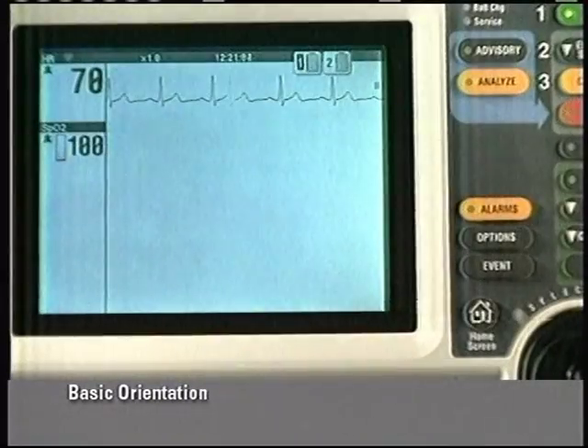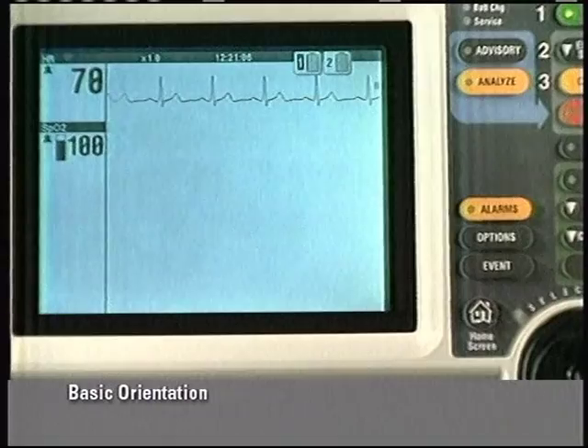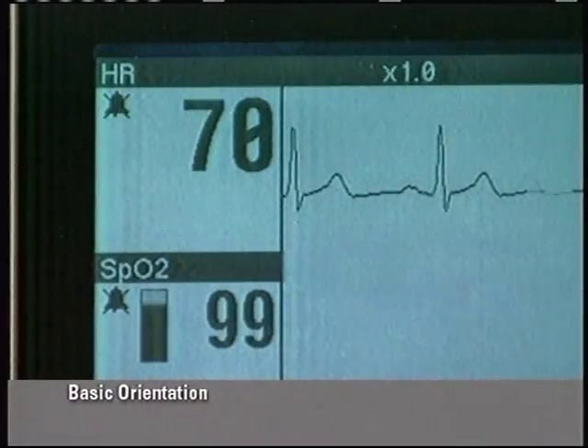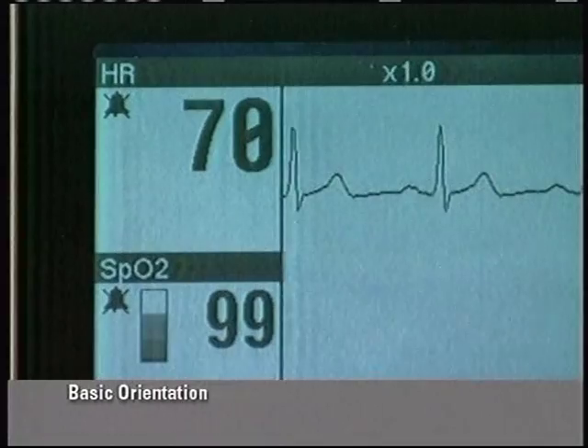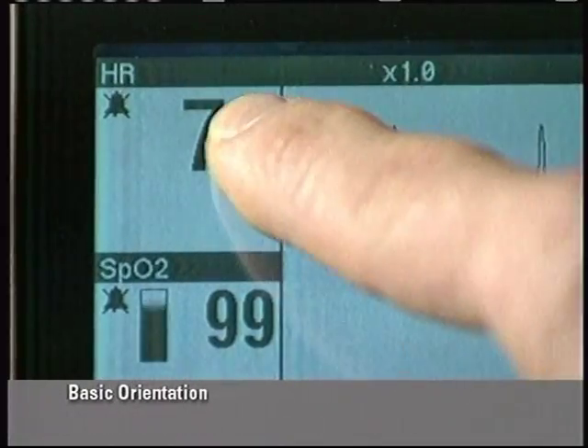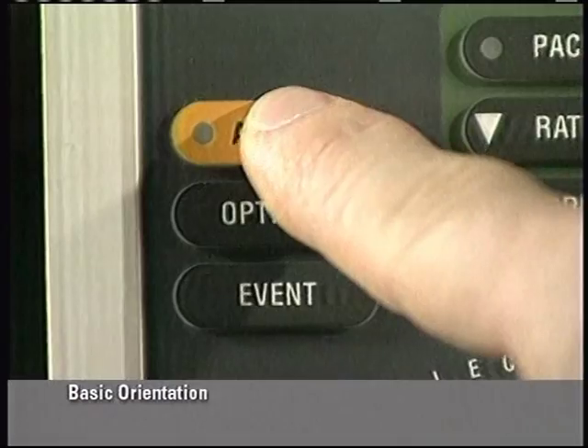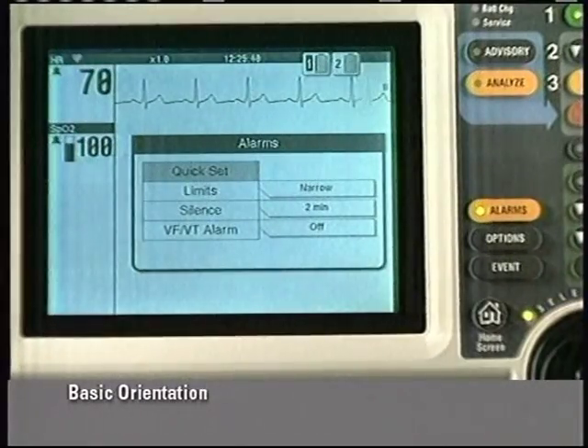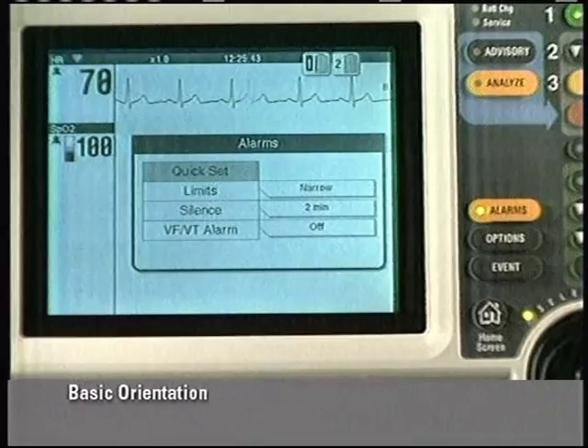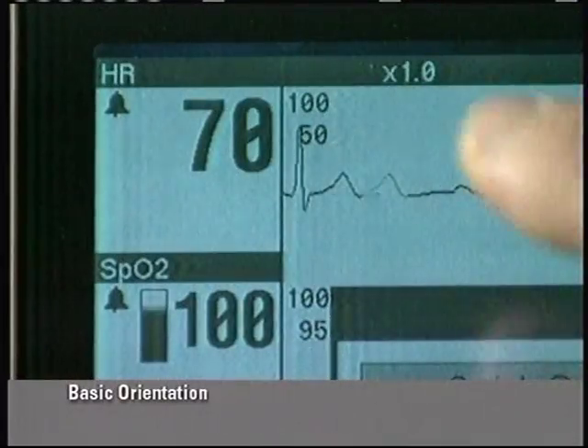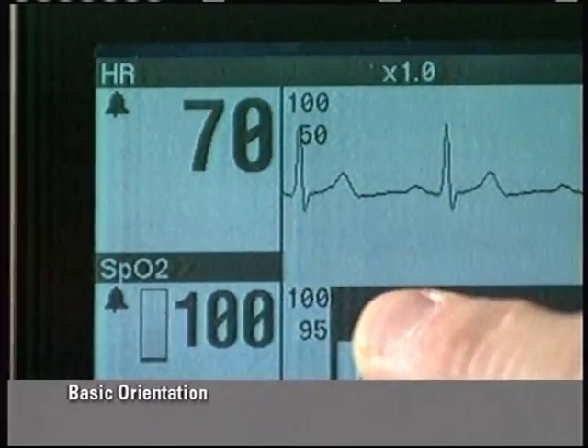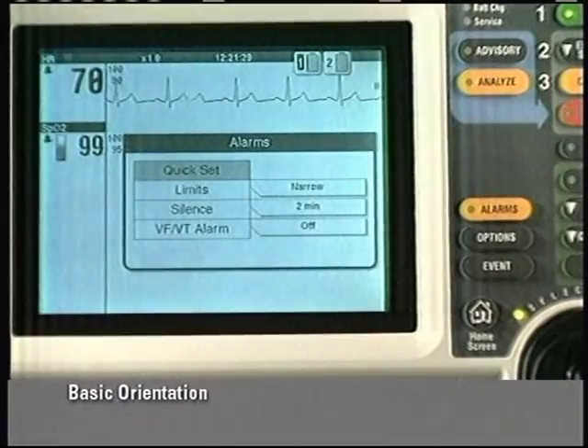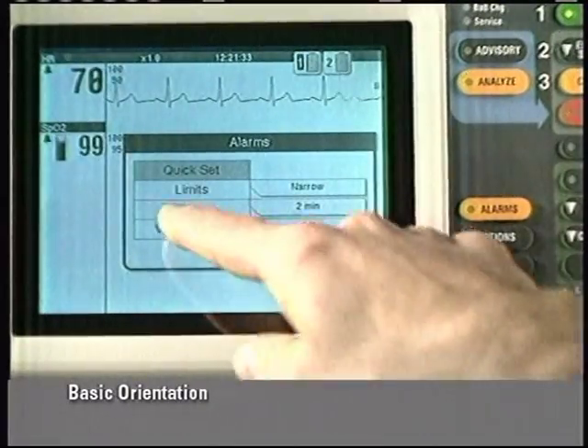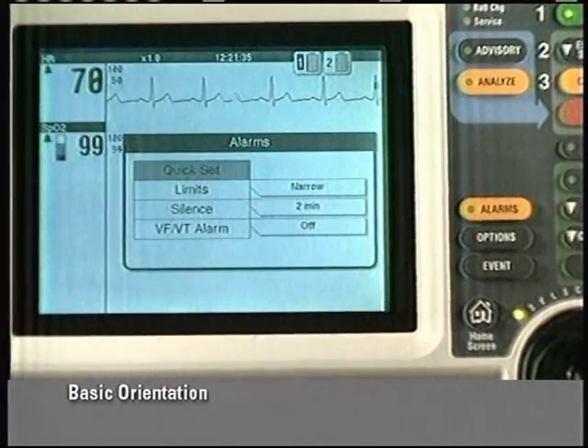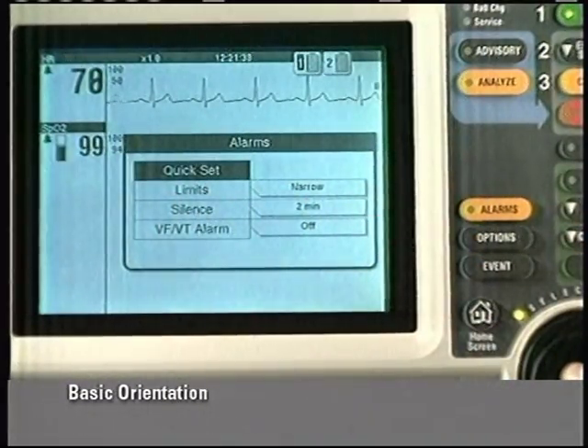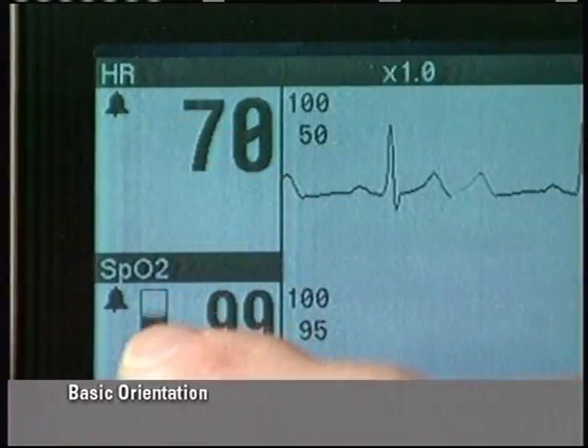The LifePak 12 defibrillator monitor features QUIK-SET alarms. QUIK-SET alarms can be configured to be on or off when the defibrillator is powered on. If QUIK-SET alarms are configured off, push Alarms to activate the alarm. The alarms menu appears. When activated, QUIK-SET automatically sets alarm limits around the patient's current vital sign values for all monitored parameters. If the limit setting is acceptable, press the selector. QUIK-SET highlights in black and a bell symbol next to the monitored parameter indicate alarms are active.